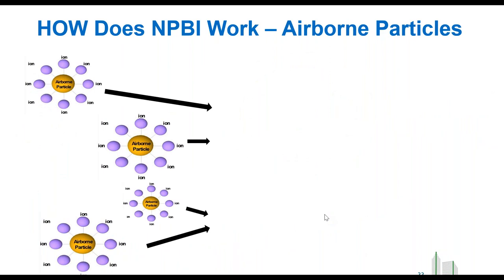Airborne particles can also be addressed with needlepoint bipolar ionization. The ions will attach to these small particles in the air, the ones that we can't see. Once they attach, they start attracting other particles of opposite polarity, and it makes them grow larger in size. We refer to this as agglomeration. Think of it like taking individual snowflakes and packing them together to make a snowball. Particles that were previously too small to be captured in a filter are now larger, like our snowball.